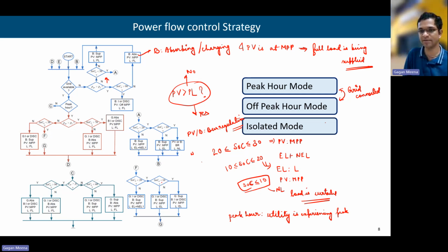If SOC is between 20 and 10, then non-essential load will not be supplied, only essential load will be supplied. And if the SOC is less than 10%, then the battery will not be used. Here, only the essential load will be met by using supply from the grid. PV will be operating at MPPT and grid will only supply the essential load, because the battery is already at 10% SOC, we cannot discharge it further.